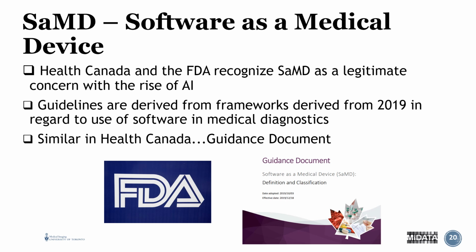Now, software as a medical device is software that behaves like a medical device and therefore is regulated like a medical device. And that's why it's called software as a medical device. So this software needs to be assessed and tested just like medical devices, and then it gets assigned a classification.